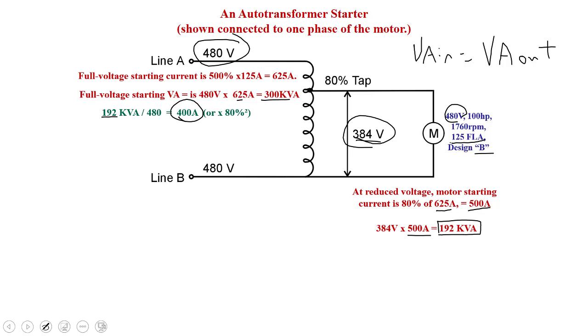We call this a double reduction because we have a high voltage on our auto transformer primary. That means we're going to have a low current on the primary of the transformer. On the secondary, we get our first reduction because we only applied 80% of the voltage. We only have 80% of the inrush current going to the motor. And VA in equals VA out.